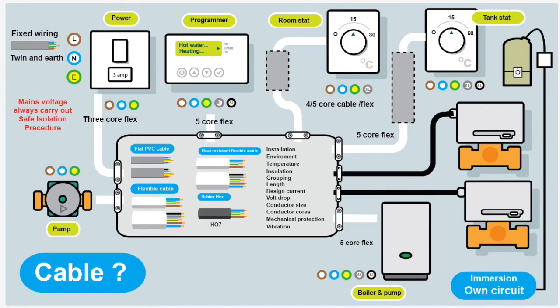There's generally two types of cables we use in domestic UK heating systems. We've got the flat PVC twin and earth type cable, which we use for the fixed wiring that goes to your fused spur, that kind of thing. And you've got your flexible cable, which we use to go through all the various different accessories. The spur, and the clock, and the pump, and the valves, they're generally in the same cupboard. So we can run flex to these cables quite easily. There's no large distance. It's often only less than a metre or more to each of the individual pieces.